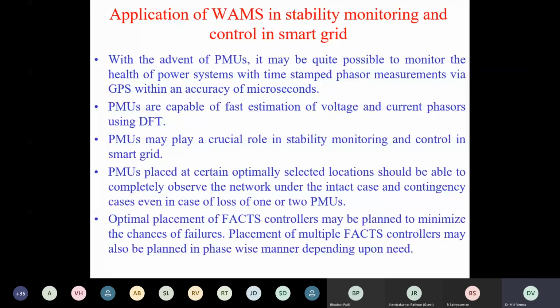Earlier we had a SCADA system. With the SCADA system, what was the problem? We are able to measure the magnitudes of voltages and currents, but we are not able to measure angles. So we are not able to measure phasors. So unless you measure complete phasors, you cannot do the analysis. So with PMU, which is providing time stamped measurement, time stamp means at the same time measurements are performed by different PMUs put at different locations, which are synchronized by GPS clock.